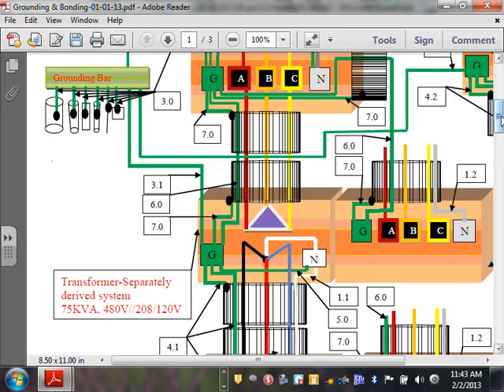I don't think you can get away with that. Did you guys do it? I'm curious. No, I'm just looking at that. Yeah. I see your point though. It makes a lot of sense because it's electrically the same point. Electrically, you're going to the same point. But typically, this conductor here, it will be coming out of the transformer going, we don't put it in a conduit; it's going separate to the grounding electrode system. But I see your point though. I really do. Anybody has? I don't think you can get away with it though.